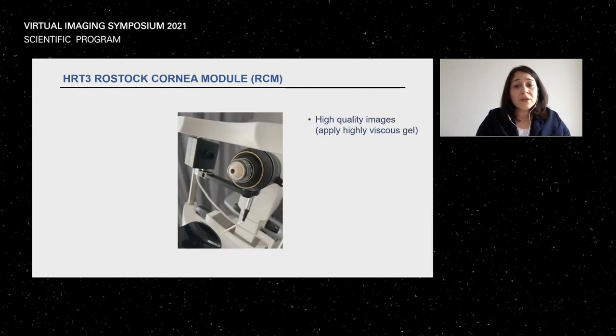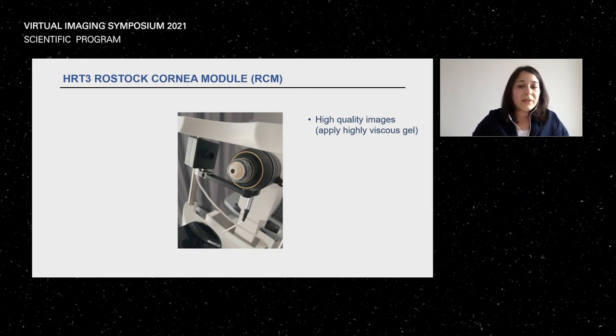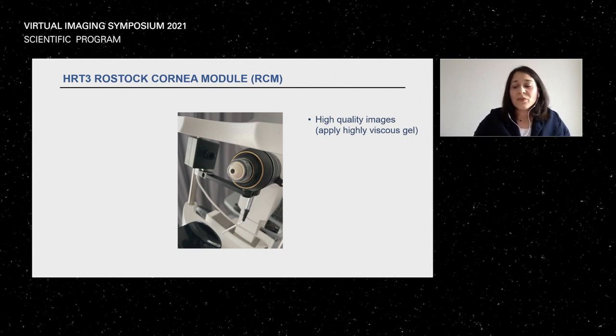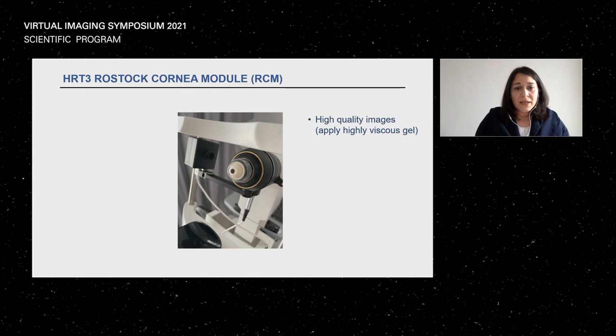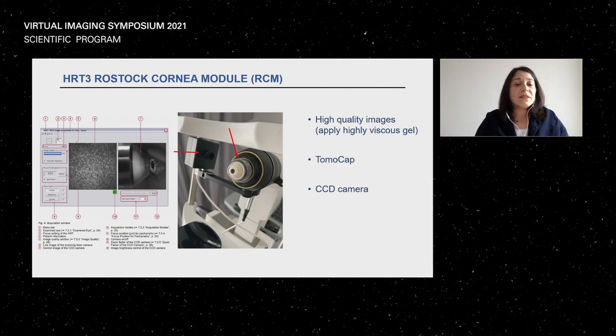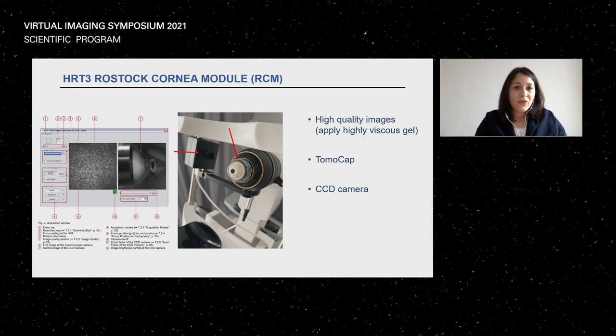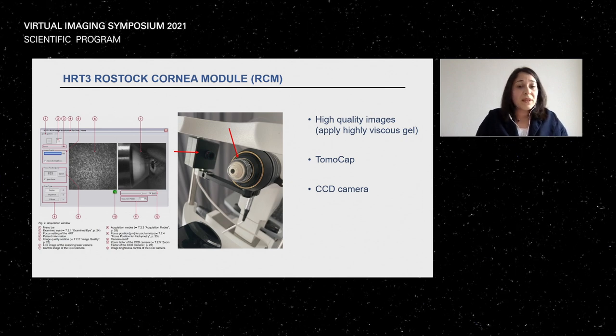Finally, you have one important screw to advance the camera towards the patient's cornea. Here you can see the objective lens. To achieve high quality images, you apply a little gel on the lens, then add a protective transparent cap on top. Before that, you give the patient anesthetic and some gel to improve image quality. On the side, you can see the CCD camera, aligned 90 degrees to the anterior surface of the TomoCap, and an acquisition window to monitor your distance from the cornea.